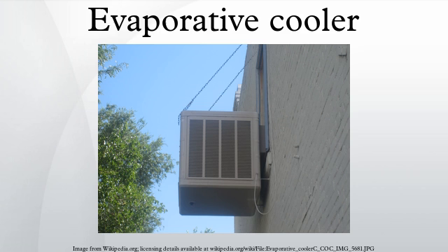Evaporative cooling is a common form of cooling buildings for thermal comfort since it is relatively cheap and requires less energy than other forms of cooling. However, evaporative cooling is only effective when the relative humidity is on the low side, limiting its popularity to dry climates. Evaporative cooling raises the internal humidity level significantly, which desert inhabitants may appreciate as the moist air rehydrates dry skin and sinuses. Exhaust ducts and/or open windows must be used at all times to allow the cooled humidified air to continually escape the home or air-conditioned area.